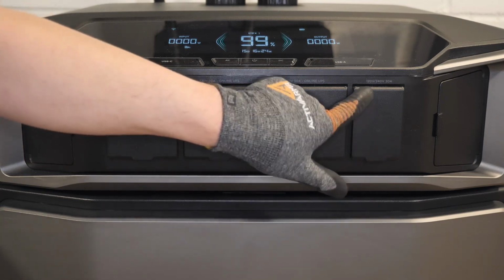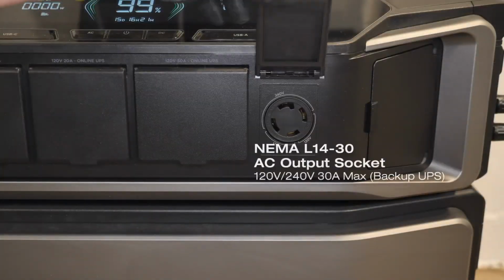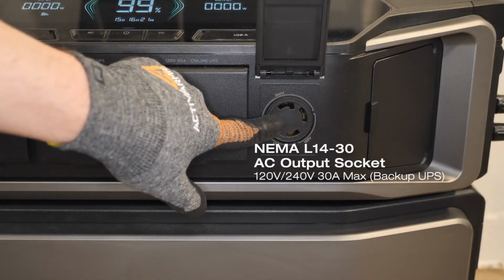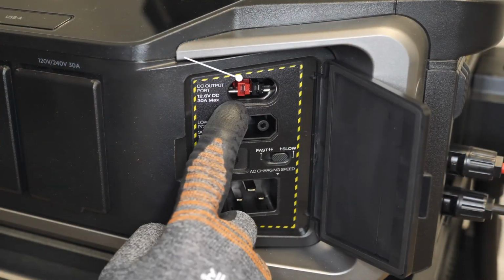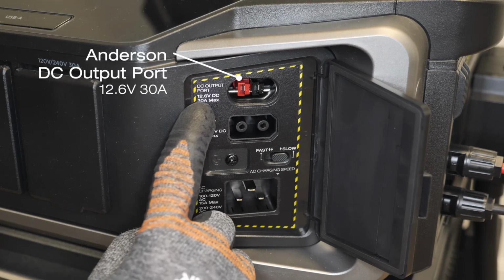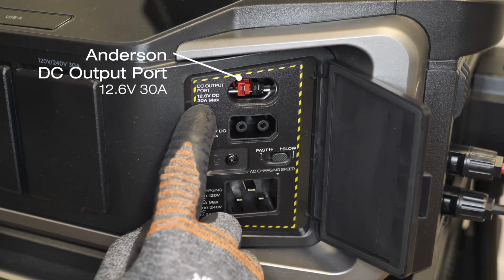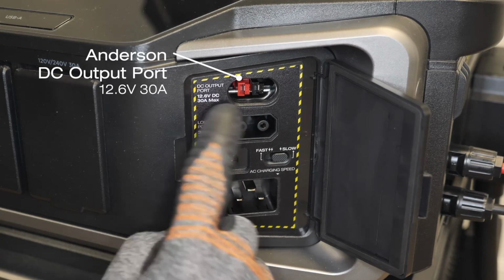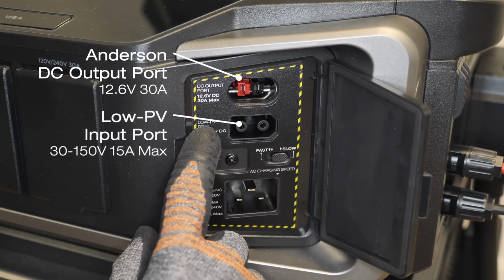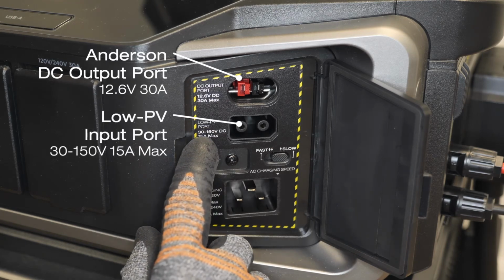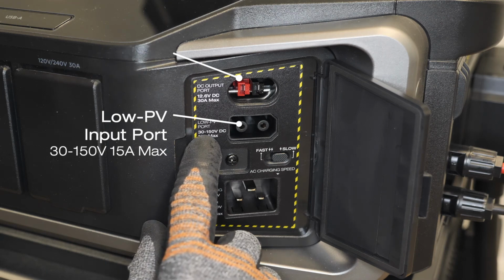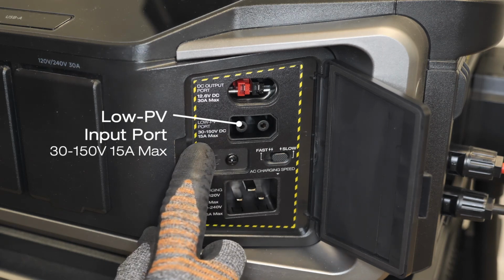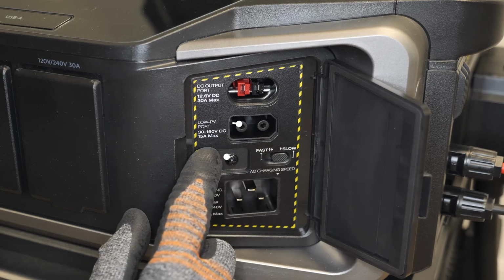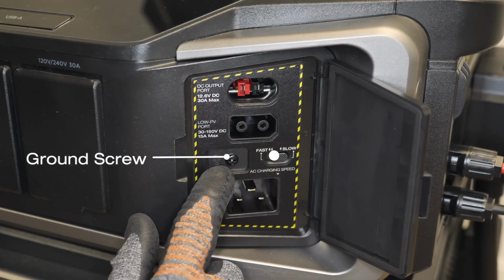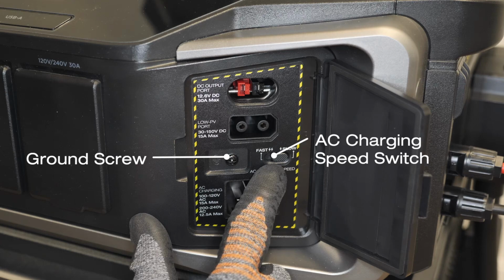This one right here is your 120/240 L14-30 output. Finally, under door number 6, at the top, we have an Anderson style port -- this is 12.6 volts and can do up to 30 amps max. Right below that we have your low PV input port, with a voltage range of 30 volts up to 150 volts DC, 15 amp max, or 1600 watts. Below that we have a ground screw, and to the right of that a fast/slow charge switch, which is adjustable inside the app.